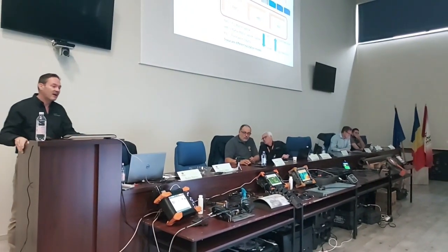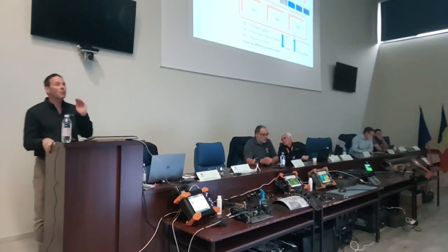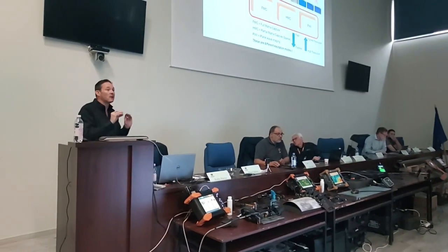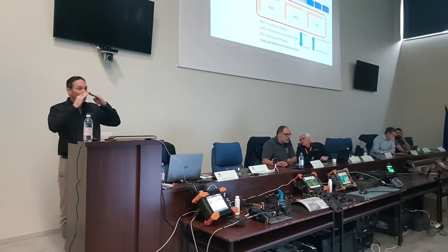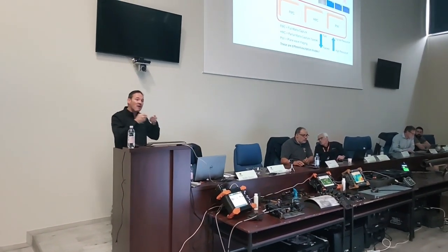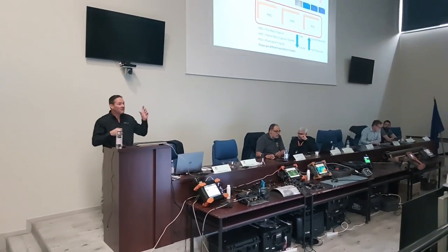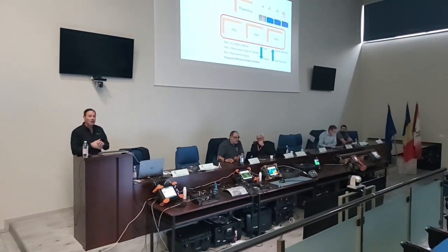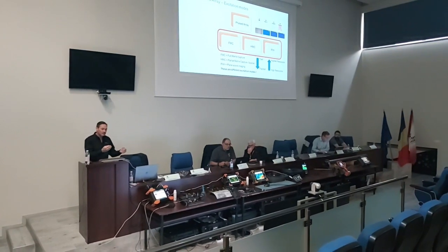There's another advantage of PWI over FMC. If we only fire one element, the amount of energy that we can get into the material is rather limited, because we only have one element, and the beam spread is quite high. With PWI, we use a wavefront, and the wavefront creates much more energy because we use the full aperture of the transducer, meaning we can inspect also thicker thicknesses.